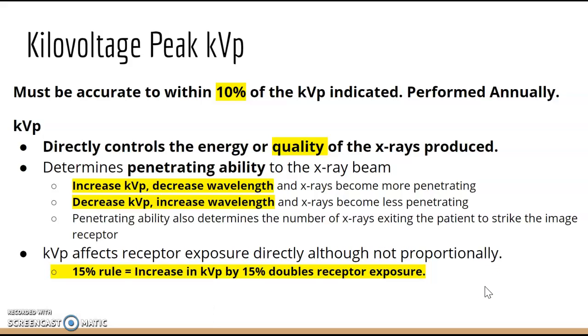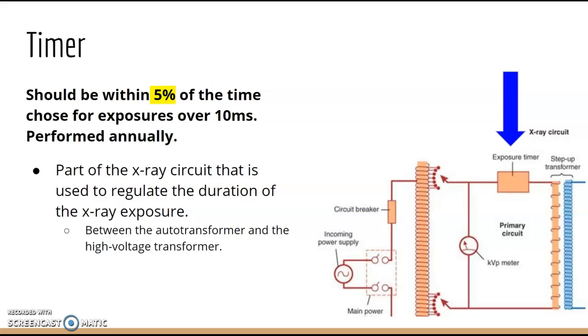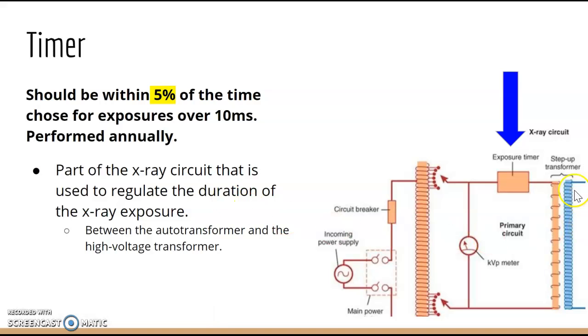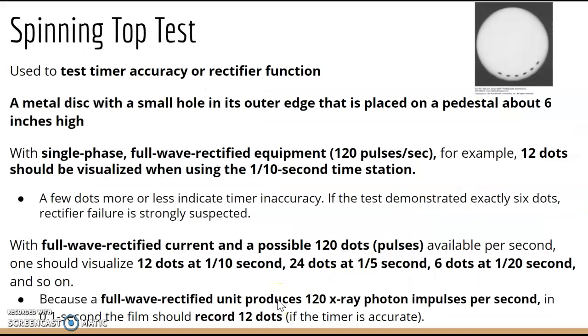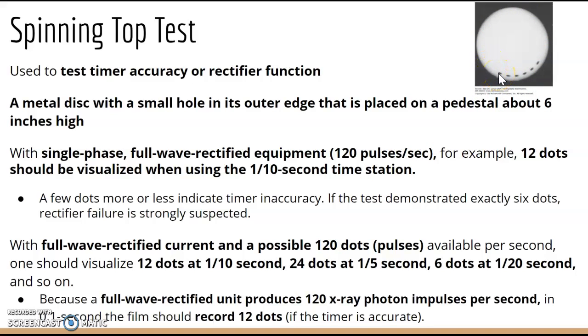The timer should be within 5% of the time chosen for exposures over 10 milliseconds. The spinning top test is one of the tests used to test timer accuracy. There are two different types: for single phase equipment, the spinning top produces dots — 12 dots at 1/10th second, 24 dots at 1/5th second.